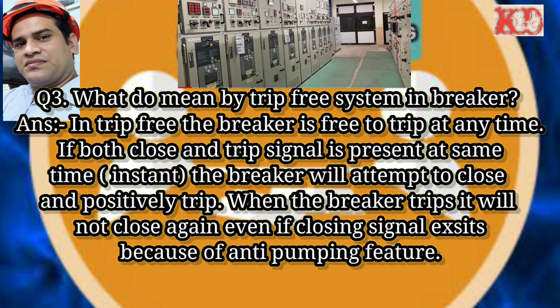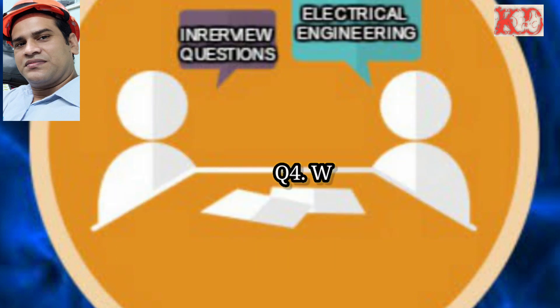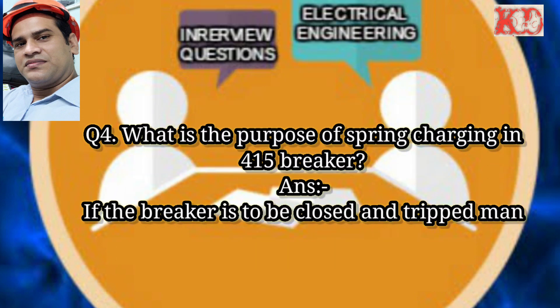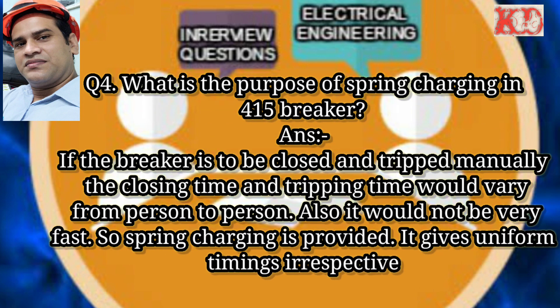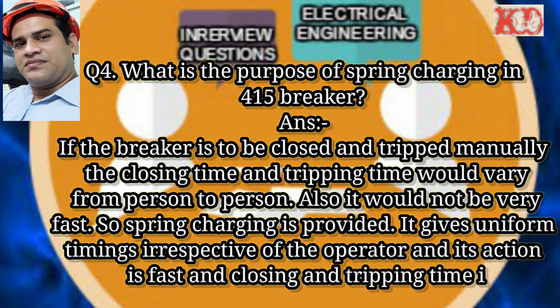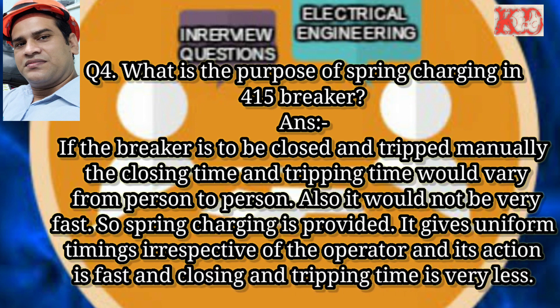Question number four: what is the purpose of spring charging in a 415V breaker? Answer — if the breaker is to be closed and tripped manually, the closing time and tripping time would vary from person to person and would not be very fast. So spring charging is provided — it gives uniform timings irrespective of the operator, its action is fast, and closing and tripping time is very less.